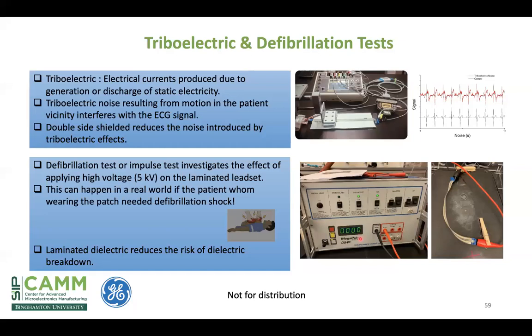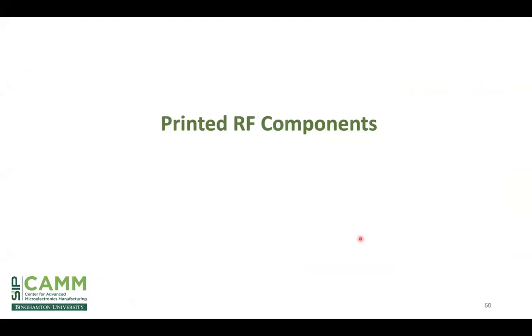In addition, if the patient were needed to be defibrillated, this is also a test that we can perform. This is a device that we have here. It literally applies the high voltage, 5 kilovolts, to this printed structure. And of course, it's supposed to withstand. And so any small defects in printing or contamination, of course, can cause it to burn up. And you don't want that to happen on a patient. And for that matter, the point of the test is not that it tests for not burning up, but that, in fact, the device will still work before and after such a defibrillating event. So a kind of a new tool for our reliability test kit.